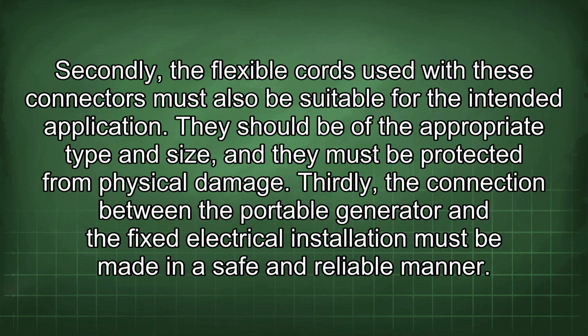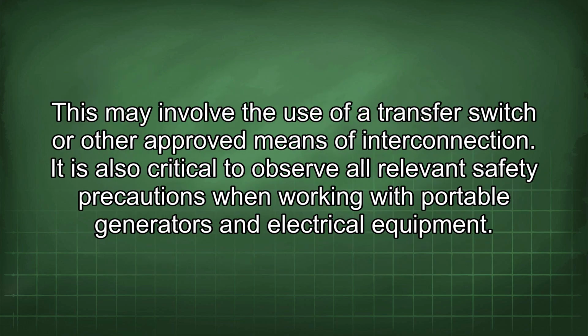Secondly, the flexible cords used with these connectors must also be suitable for the intended application. They should be of the appropriate type and size, and they must be protected from physical damage. Thirdly, the connection between the portable generator and the fixed electrical installation must be made in a safe and reliable manner. This may involve the use of a transfer switch or other approved means of interconnection.